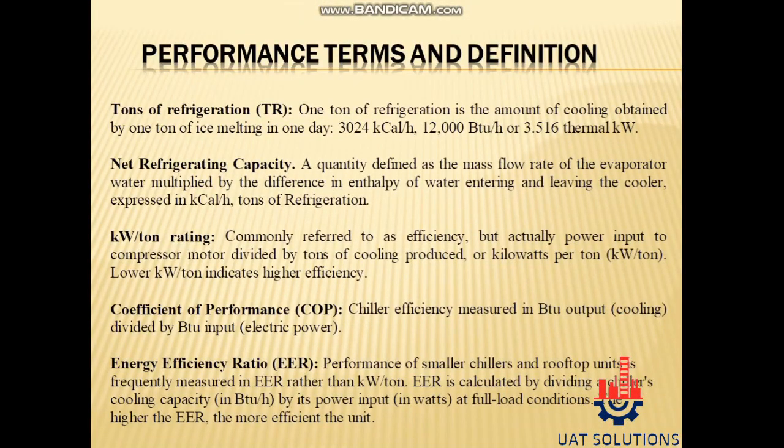Performance terms and definitions. Tons of refrigeration: 1 ton of refrigeration is the amount of cooling obtained by 1 ton of ice melting in one day — 3024 kcal per hour, 12,000 BTU per hour, or 3.516 thermal kilowatt.